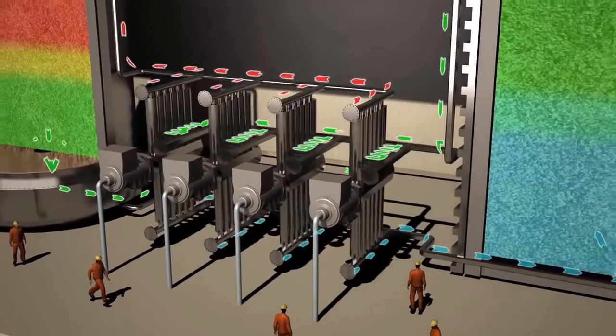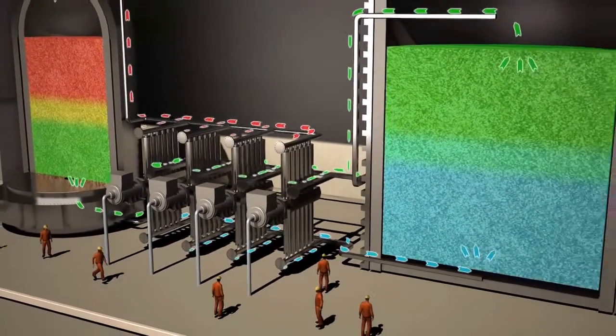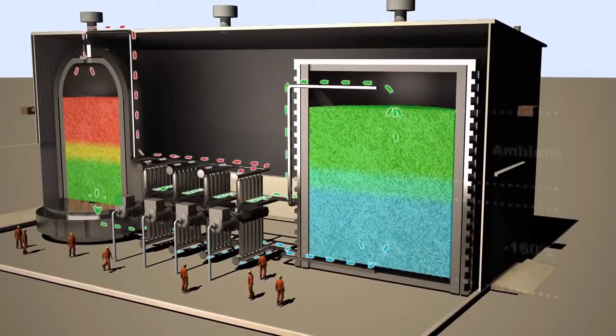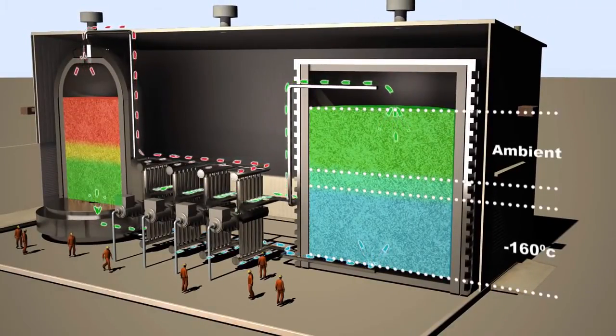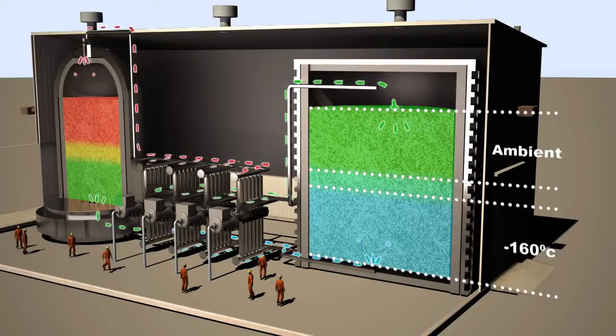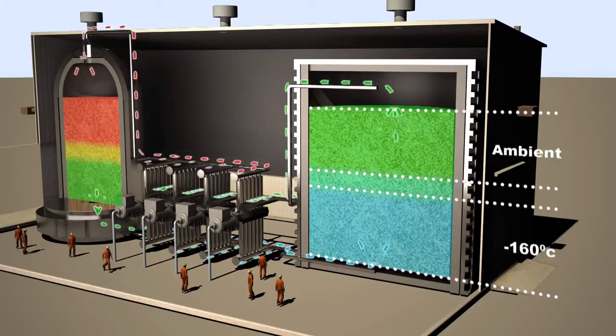It permeates the gravel storage medium, this time simultaneously warming the gas and cooling the medium. The lower zone is at minus 160 degrees, and the upper zone is at ambient temperature. In between is a cold thermal front, which gradually moves upwards during the charging cycle.